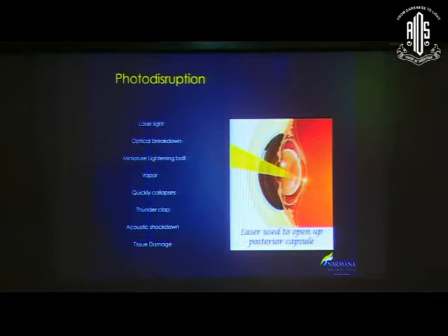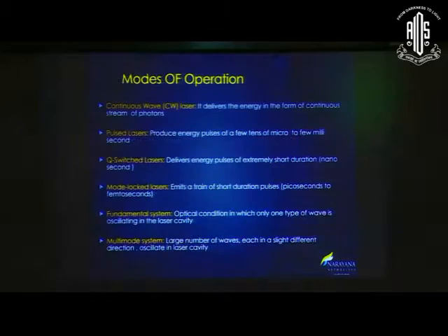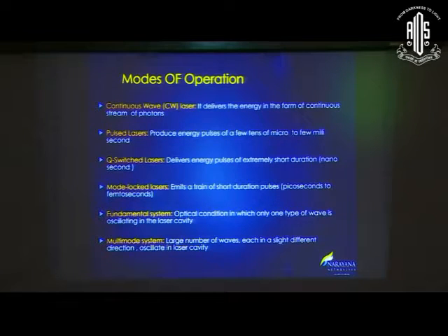And photodisruption: the laser light goes on to optical breakdown, a miniature lightning bolt happens, there's vapor, this quickly collapses, there's a thunderclap, an acoustic shock wave, and tissue damage. This is the type that is used to open up the posterior capsule. Going on to the modes of operation of lasers, you have continuous, pulsed, Q-switched, mode-locked lasers, fundamental systems, and multimodal systems. Each one of them is used for different types of lasers and deliveries.